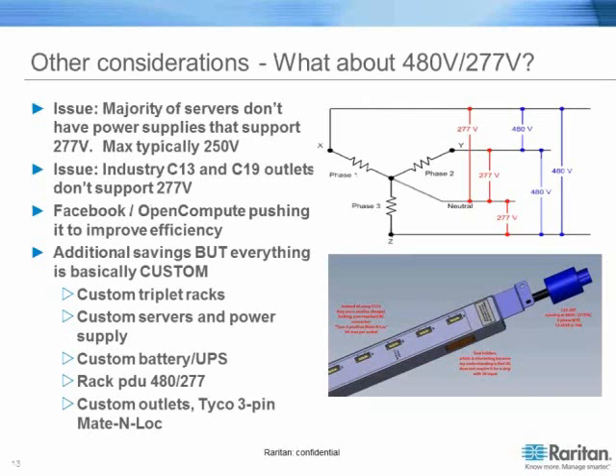Now, what goes beyond 415? We've had some customers talk about 480, 277, literally coming right from the power plant. One of the problems we see here is your industry standard C19, C13 plug simply won't handle this. It isn't feasible right now for an off-the-shelf deployment. Facebook, some open computing groups, have pushed this because it gives an additional percentage of efficiency at the rack level. However, almost everything off the shelf out there, whether it be the PDU, the server plugs, the UPS, the outlets, and everything else, is not available in an off-the-shelf solution.